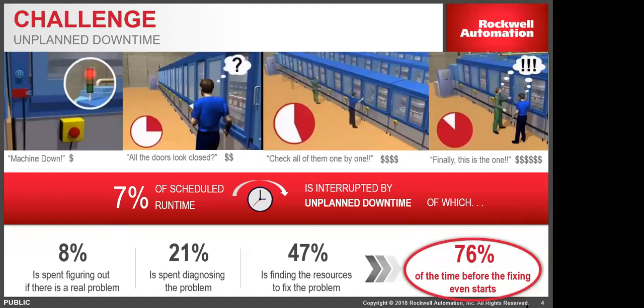When you're running a plant, traditionally, most of the time when you are connecting safety devices, customers try to use them in series. The reason is if you have a number of safety devices, you don't want to take up too many I/O points in your relays or your safety controller. So customers connect everything and wire them in series. What happens is if any of those devices go down, because it's connected in series, you don't know exactly where it goes down, right?